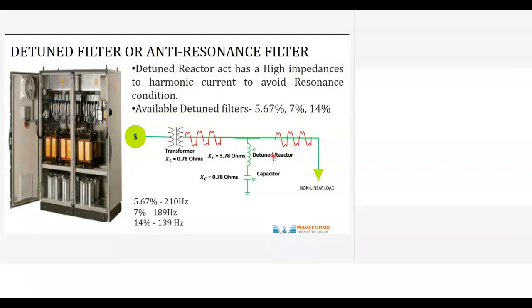So sometimes these filters may not be suitable. If there are multiple harmonics of higher magnitude, then these filters can heat up and can burn up sometimes. So if the harmonics are not very high, these filters are okay. But otherwise, if there are harmonic-rich loads, say about 20%, it may not be an ideal filter. So you'll have to resort to some other method or technique.